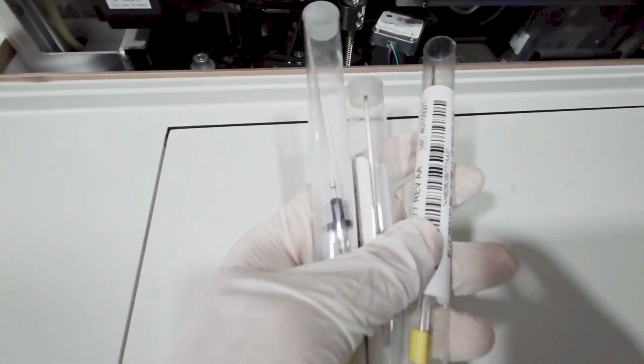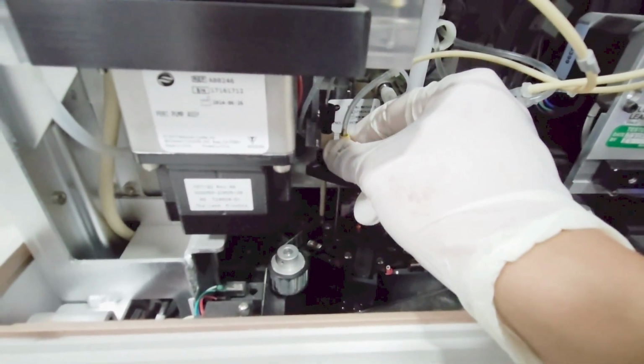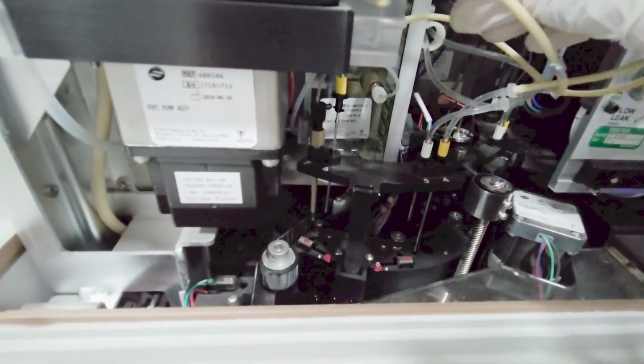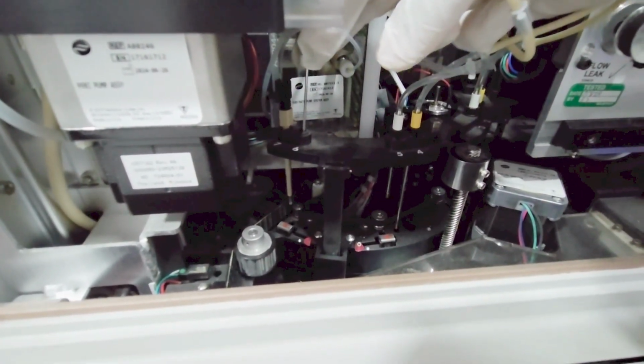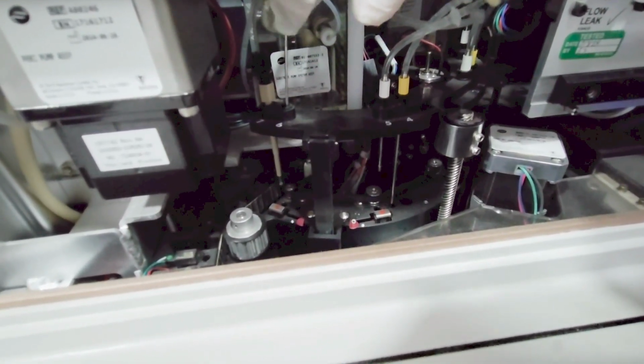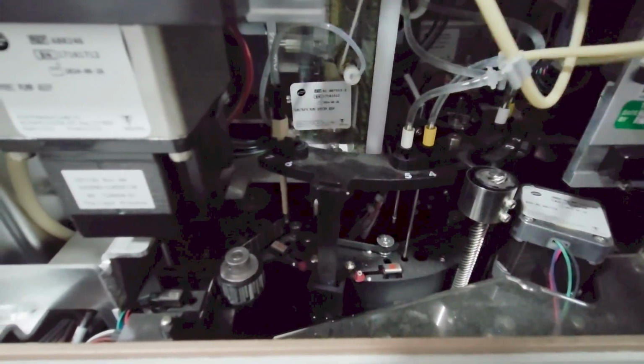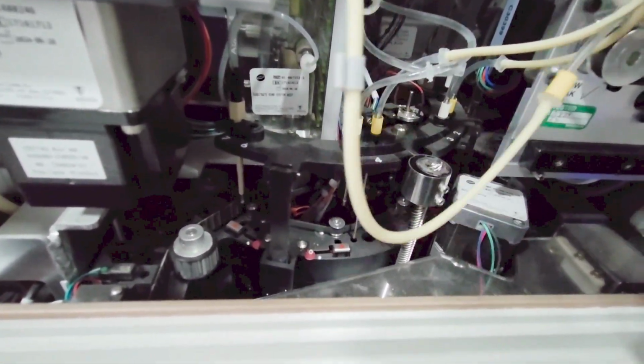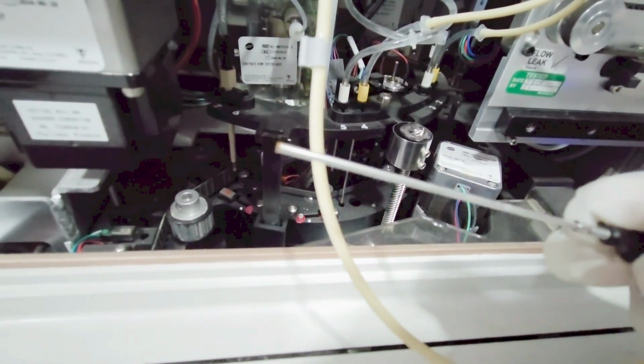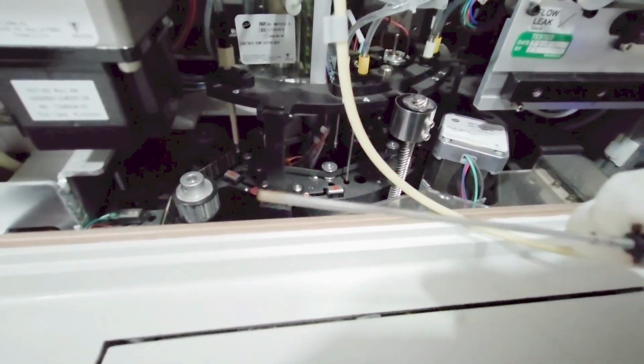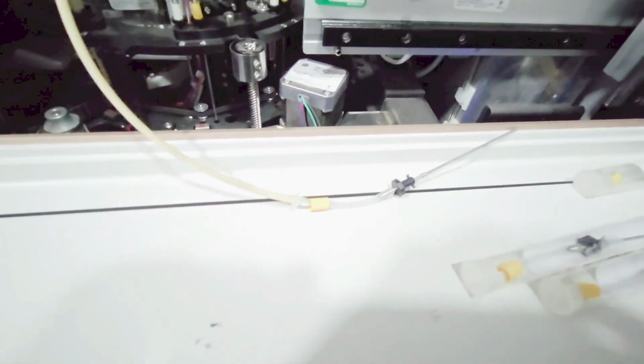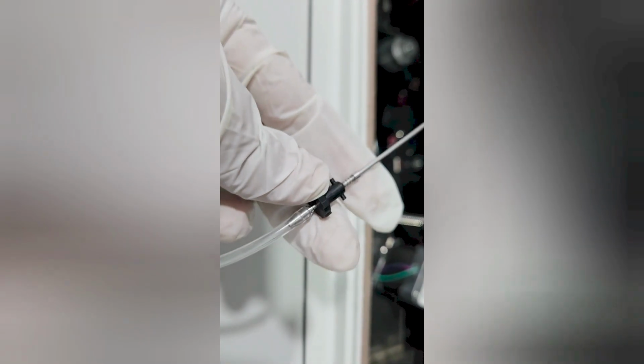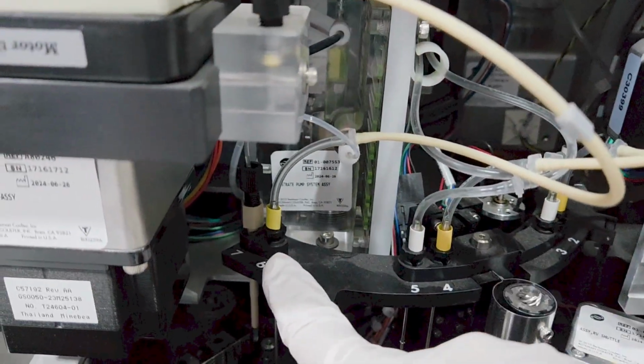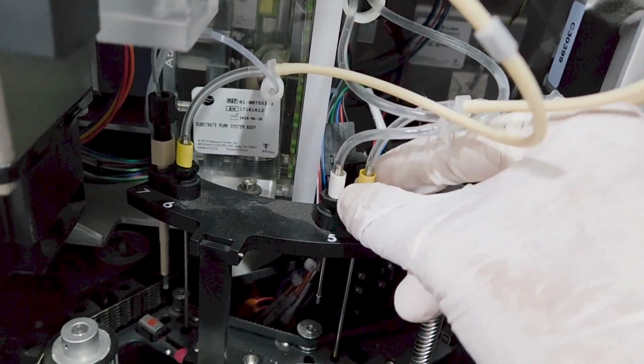Before we begin removing them, there is an important component to note, and that is a small black clip which is located just below the screw that secures each probe. This clip needs to be rotated anti-clockwise and gently pressed downward in order to release the probe from its position. Let me demonstrate this step for you. As you can see here, after rotating the clip and pressing it down slightly, the probe is easily released.